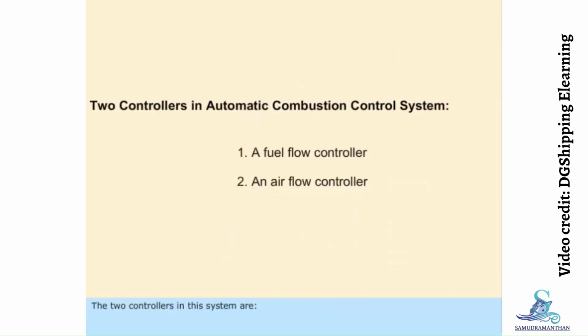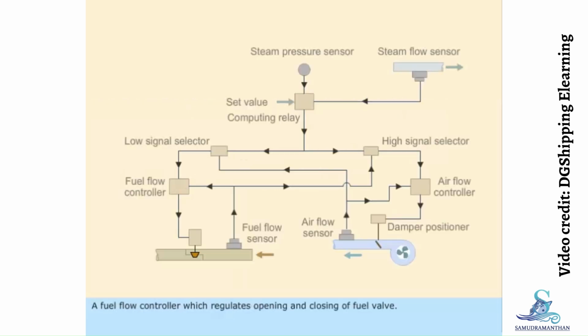The two controllers in this system are a fuel flow controller, which regulates opening and closing of fuel valve, and an airflow controller, which regulates the airflow by opening and closing of dampers. The steam pressure and the flow signals are transmitted to a computing relay. The computing relay generates the master signal depending on the load of the boiler. This master signal represents the fuel requirements to the boiler.